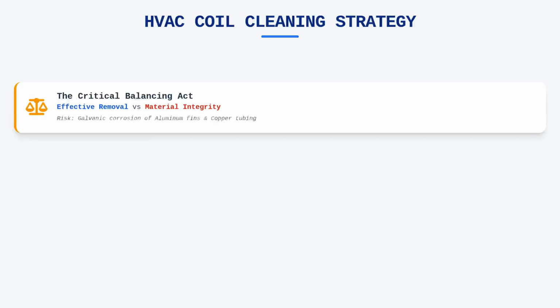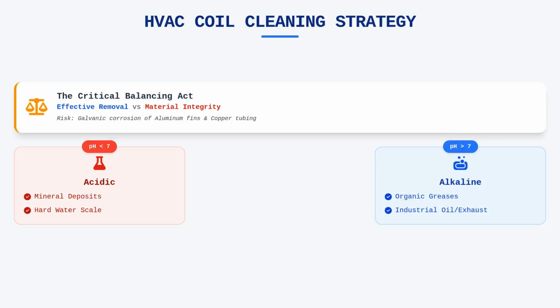When we approach the task of cleaning HVAC coils, we are essentially performing a balancing act between effective contaminant removal and material integrity. The primary challenge is that coils are constructed from reactive metals, usually aluminum fins bonded to copper tubing, which can easily suffer from galvanic corrosion if exposed to the wrong chemical agents. We categorize cleaners into acidic, alkaline, and neutral solutions, each serving a specific purpose based on the type of debris found on the coil. Acidic cleaners are generally effective at removing mineral deposits and hard water scale, while alkaline cleaners excel at breaking down organic, greasy, and oily residues common in kitchen or industrial exhaust environments.